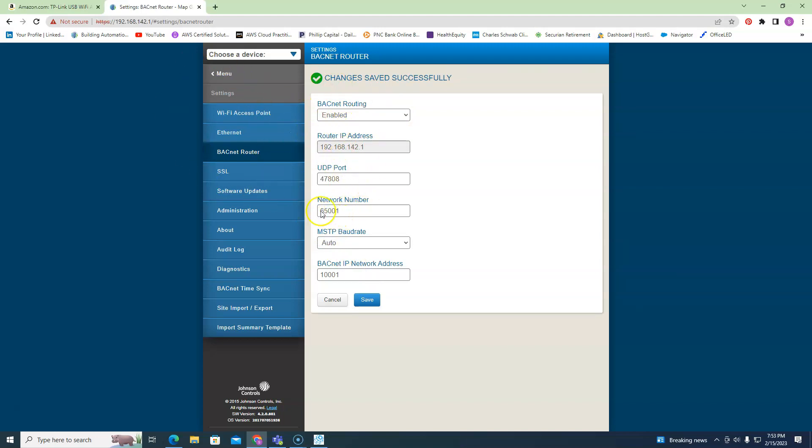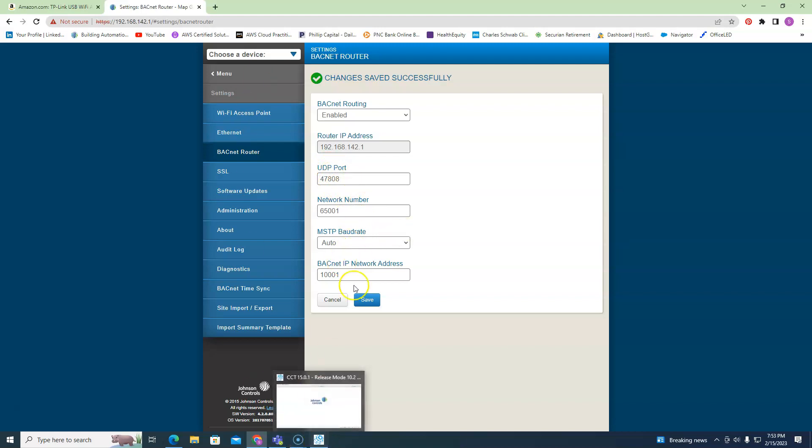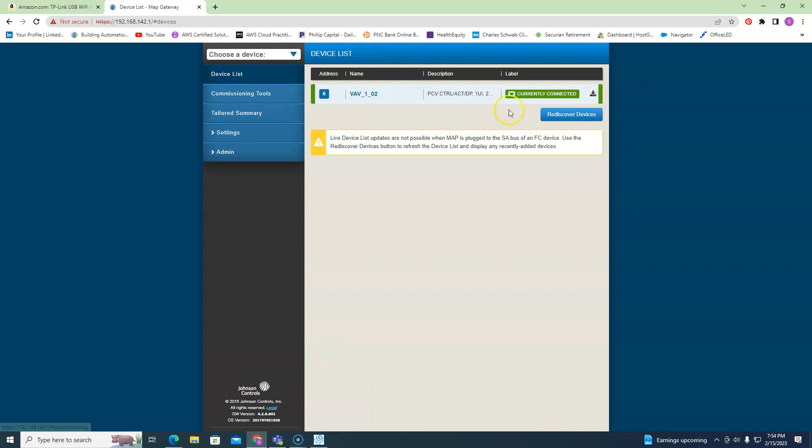Double-check your network number, double-check your UDP port. Make sure you didn't change it or someone didn't change it on you. And then you should be good to go. If you can see it here and those settings are correct, it's not the MAP Gateway.